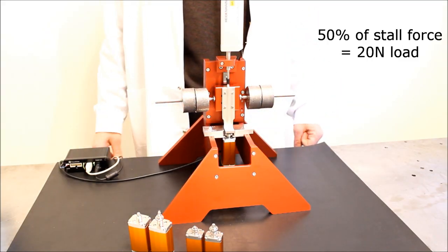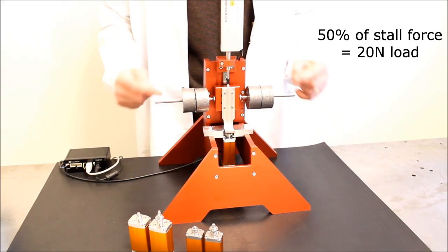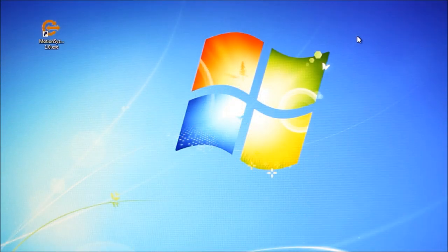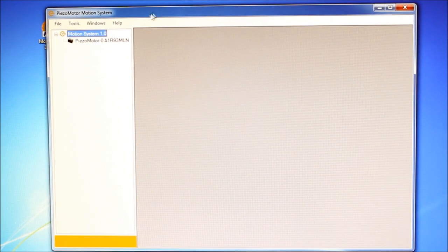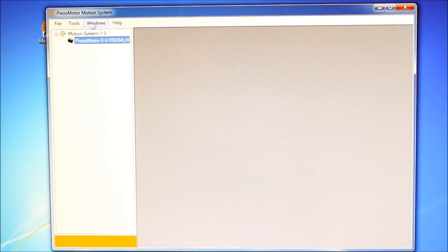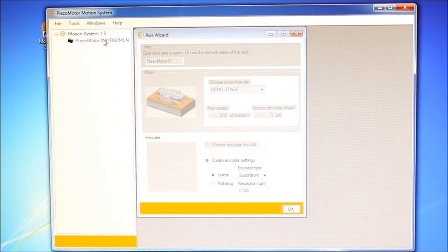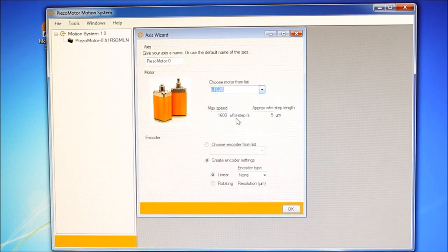We will run the motor with a force of 20N. The PiezoMotor motion system software is started on the PC. The connected driver shows up in the tree view. In the axis wizard, we select the motor and configure the encoder.